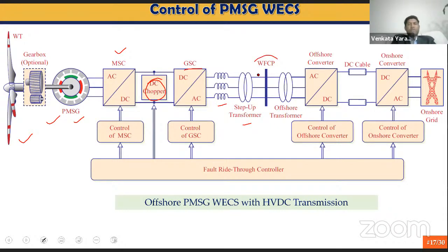This is called the wind farm collection point. That's where several other turbines are connected. And then we have this wind farm collection point connected to the onshore grid through an offshore converter, which is AC to DC. This is operating at very high voltages because we have the offshore transformer increasing the voltage to 130 kV or 230 kV. And then we transmit the power with DC cables, usually submarine cables. Once the cables reach onshore, we convert the DC back to AC, and then we connect the AC output to the onshore grid.